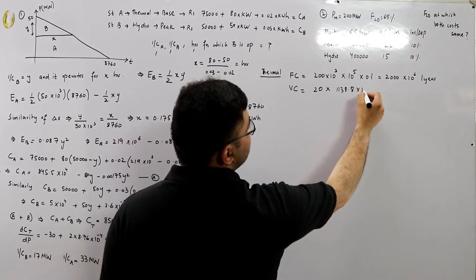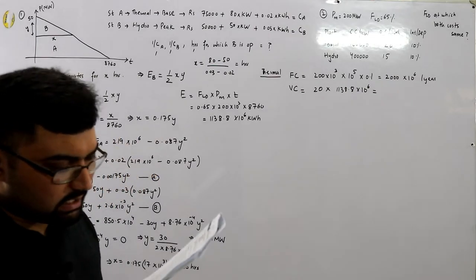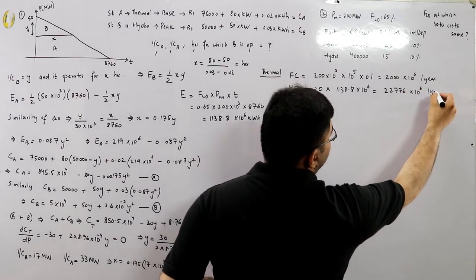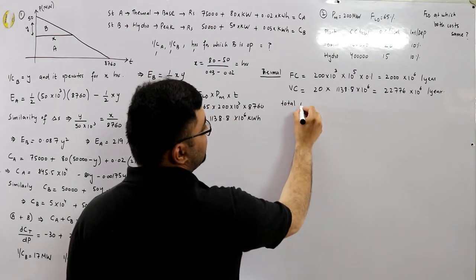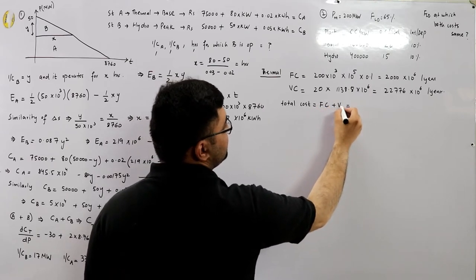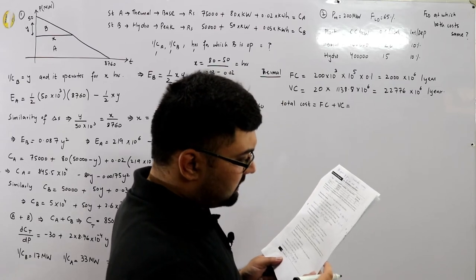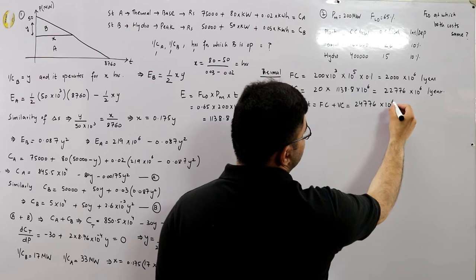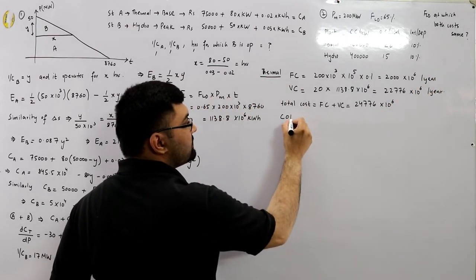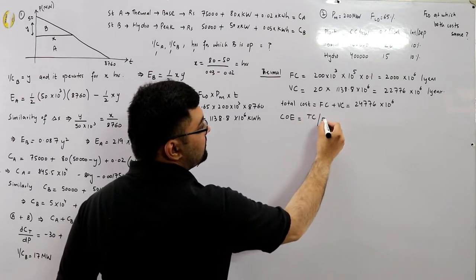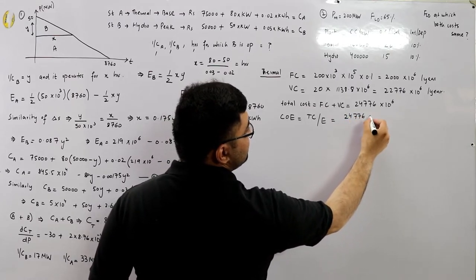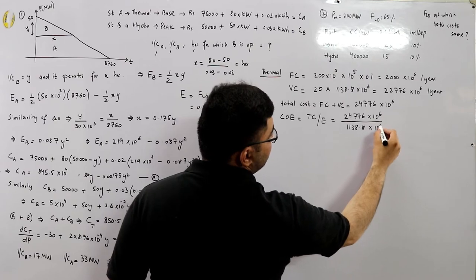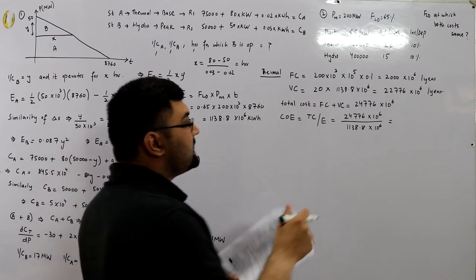Variable cost for thermal = 20 × 1138.8 × 10⁶ = 22,776 × 10⁶ rupees per year. Total cost = fixed + variable = 24,776 × 10⁶ rupees per year. Cost of electricity = total cost / energy units = 24,776 × 10⁶ / 1138.8 × 10⁶ = rupees 21.75 per kilowatt hour.